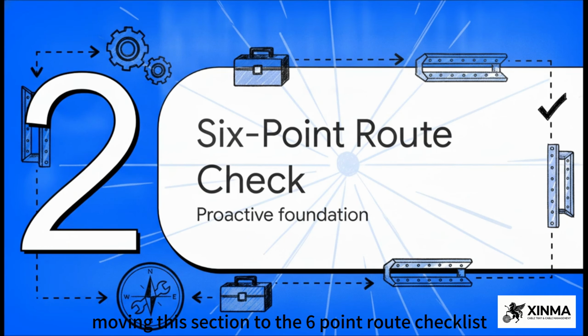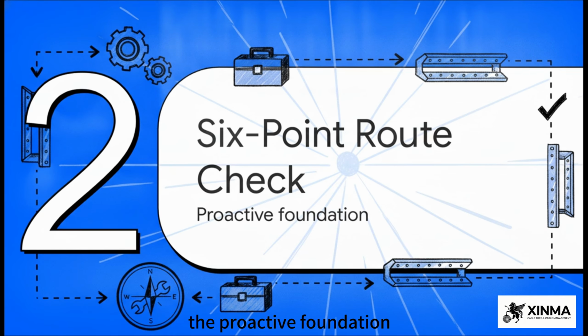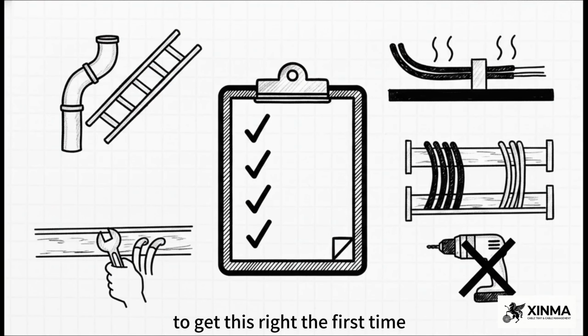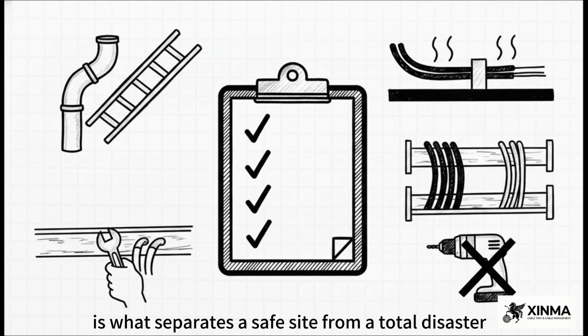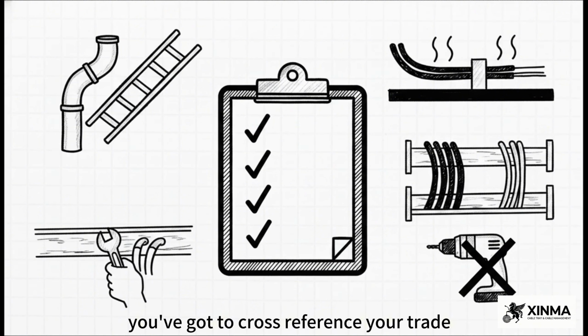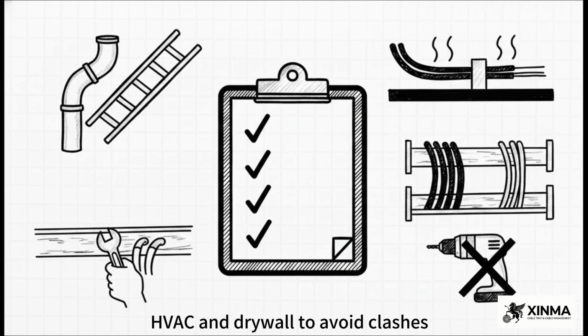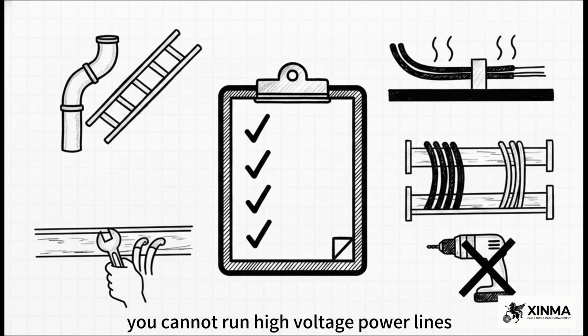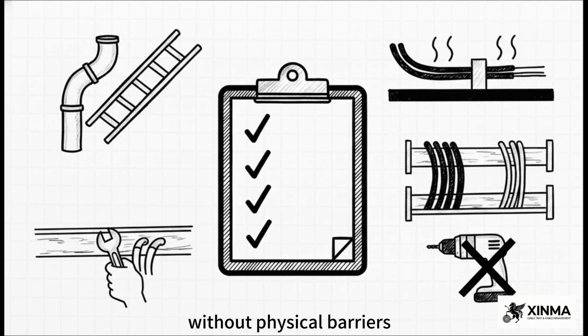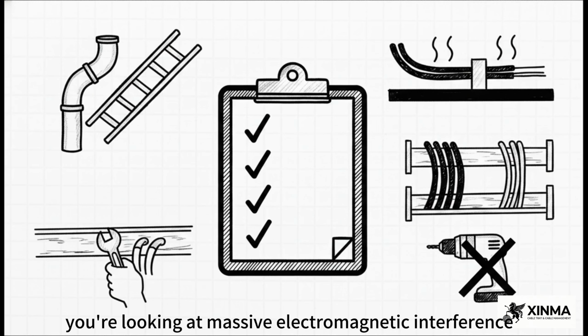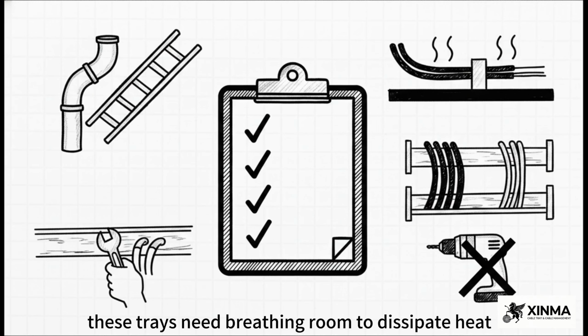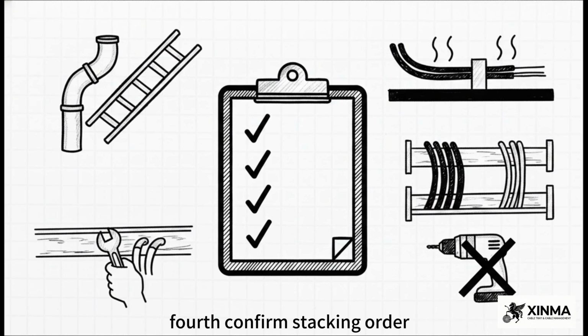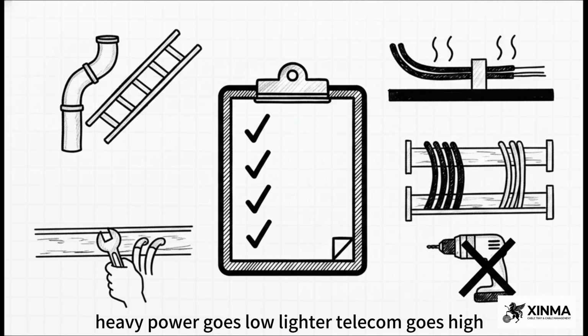Moving to Section 2, the 6-point route checklist, the proactive foundation. To get this right the first time, you absolutely need a strict framework. Let's walk through this checklist, because doing this math is what separates a safe site from a total disaster. First, coordinate all routes. You've got to cross-reference your tray path with plumbing, HVAC, and drywall to avoid clashes. Second, verify segregation. You cannot run high-voltage power lines right next to sensitive data cables without physical barriers. Otherwise, you're looking at massive electromagnetic interference. Third, check your clearances, because these trays need breathing room to dissipate heat. Fourth, confirm stacking order. Heavy power goes low, lighter telecom goes high.